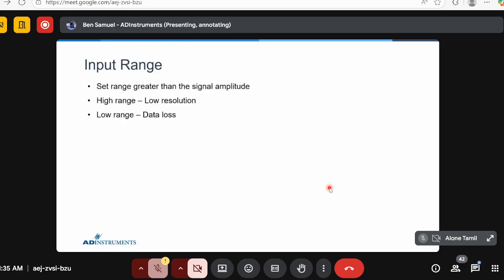So going into the next aspect, input range. To accurately record a signal, it is important to set a proper range. Many systems use gain when looking at an amplified signal. Range is inversely proportional to gain, and is a more useful concept than gain because it relates directly to the signal. So we will come to that. You set the range greater than the signal amplitude. You know the amplitude of your signal, so you set a range accordingly. If you set a high range, you can still see the data, but the resolution will be very poor. But if you set a low range, there will be data loss.